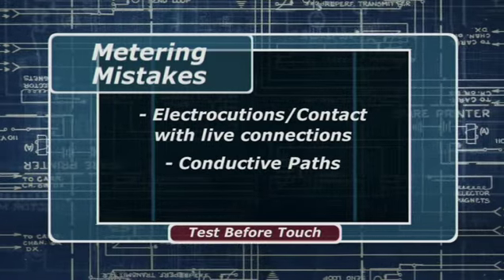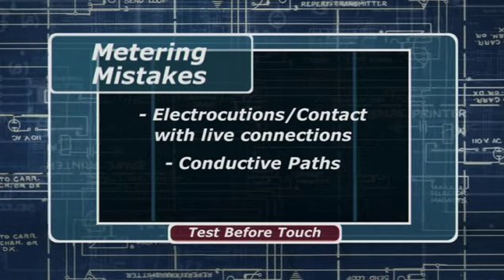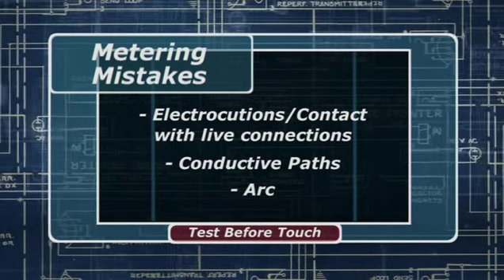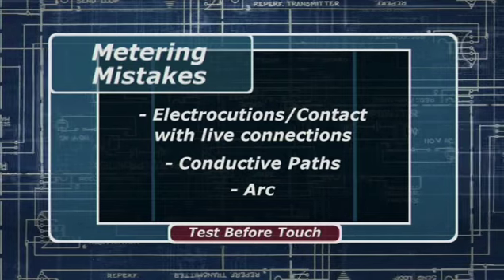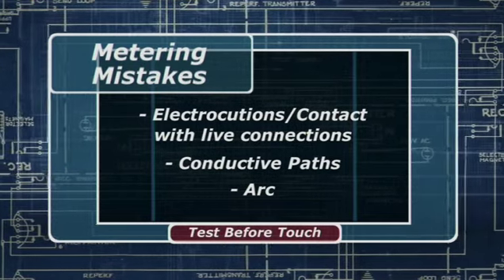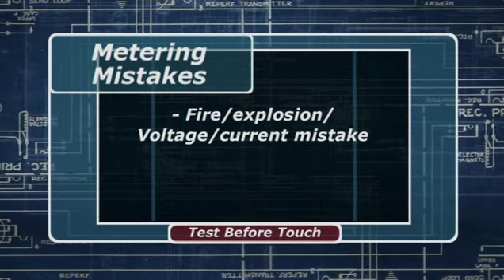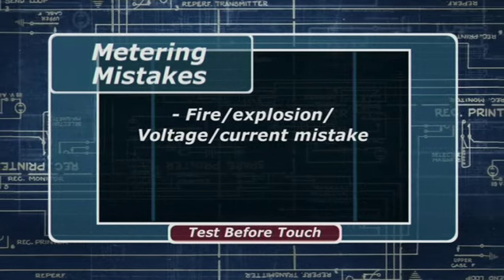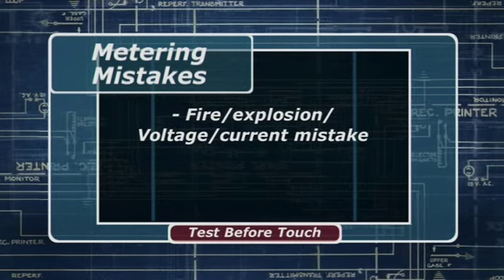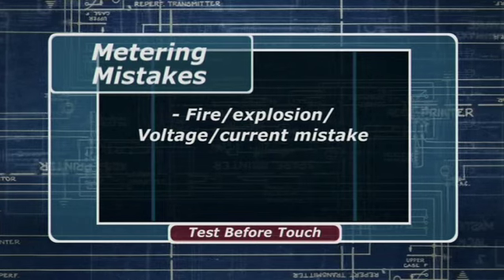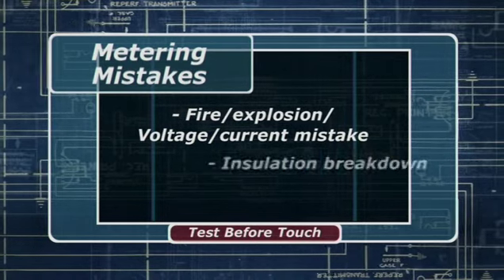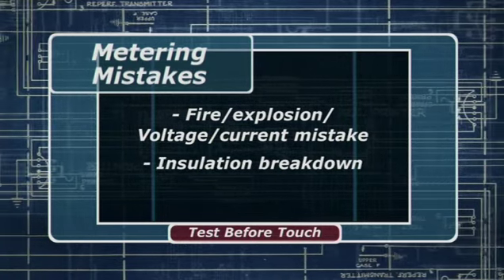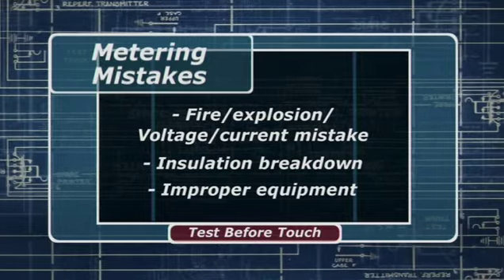You can be electrocuted from conductive paths caused by moisture or contaminants. Should a test lead become dislodged and come in contact with a conductive object, an arc could occur. And when the leads of a meter intended to measure voltage are inadvertently plugged into the jacks for measuring current, fire or an explosion can happen. The same disastrous results can occur should voltage transients break down the insulation in the meter or in the leads. Man, I had no idea.